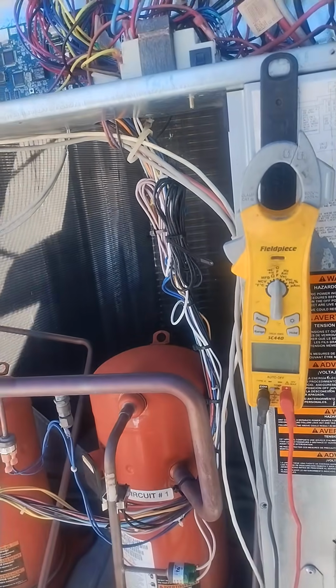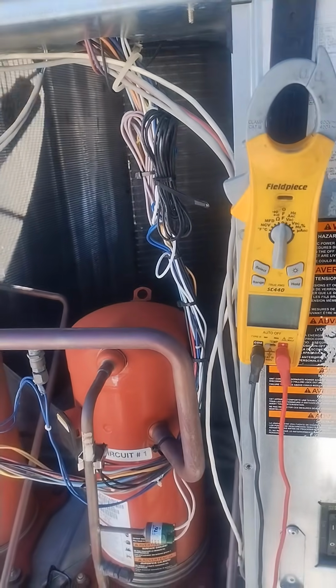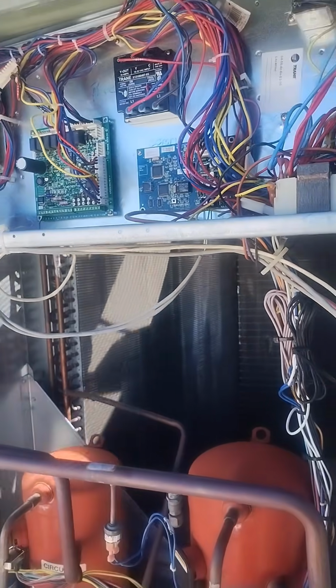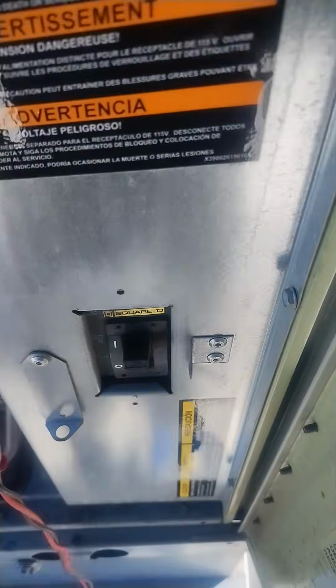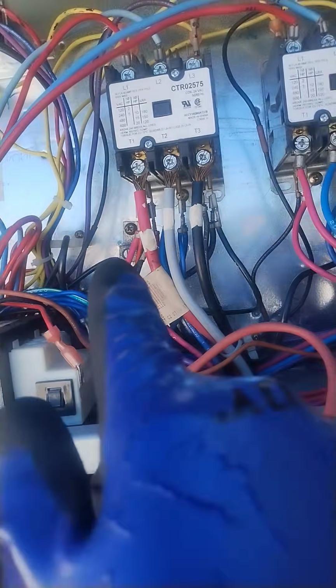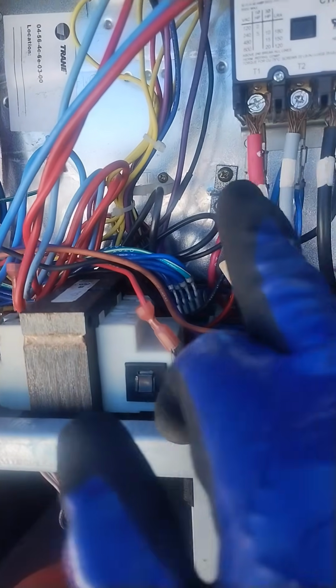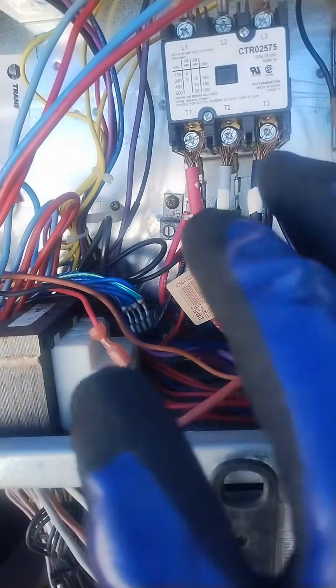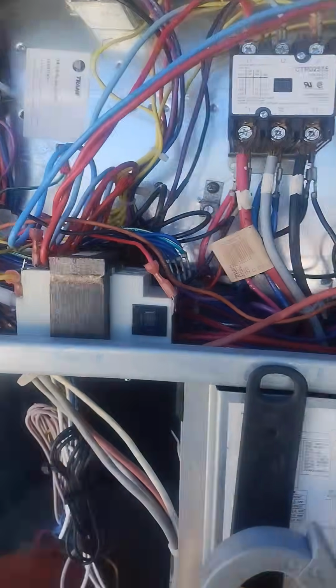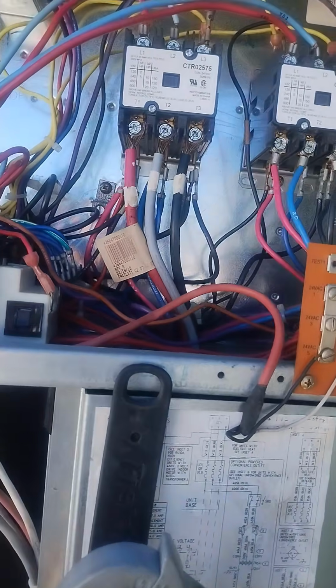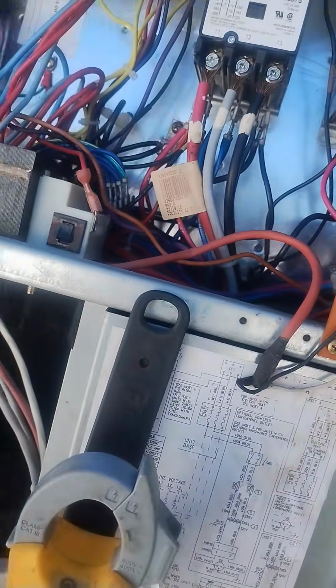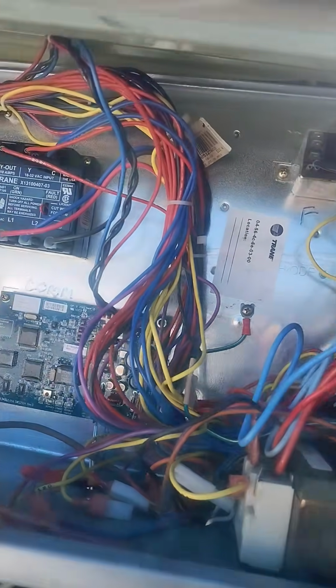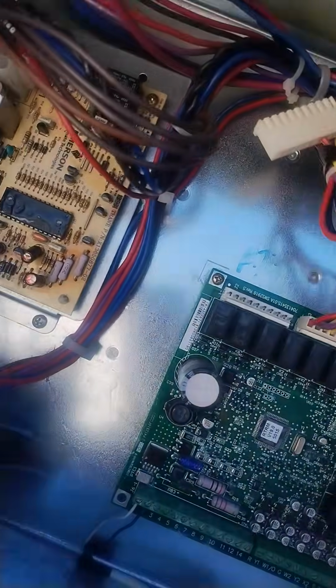So I said, okay, before I go downstairs and look for an indoor breaker, let me make sure I'm good up here. So I reset the unit right here, and the first thing I did was I checked for the main power on the line side of this contactor, the line side of it, not the load side. So I had power between all three of these. I checked every which way, power was good. Okay, so I do got power to the unit, so I don't have to go downstairs and find any indoor breaker. So I know that, like I said, I didn't have any lights on anything, no lights.